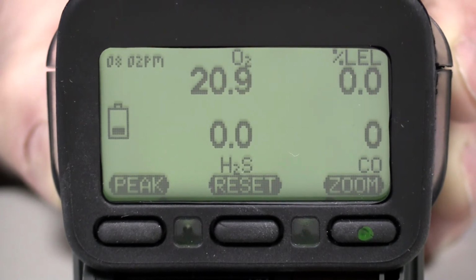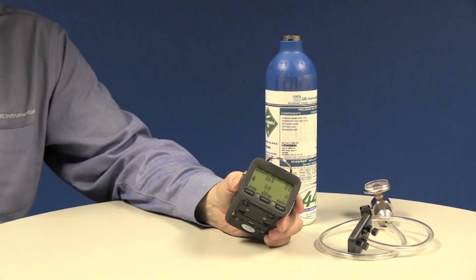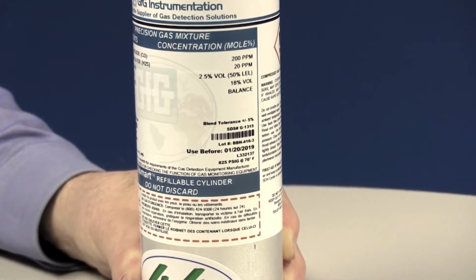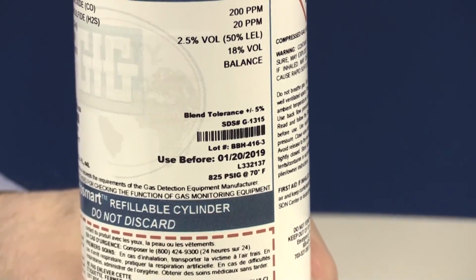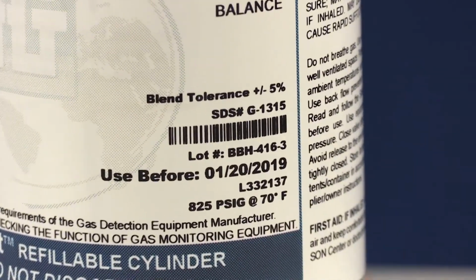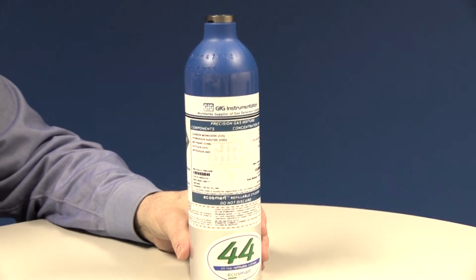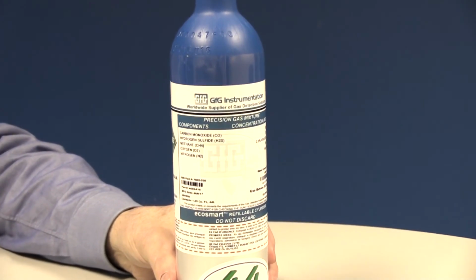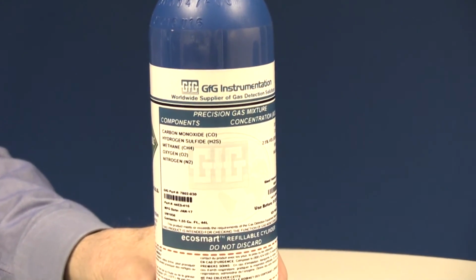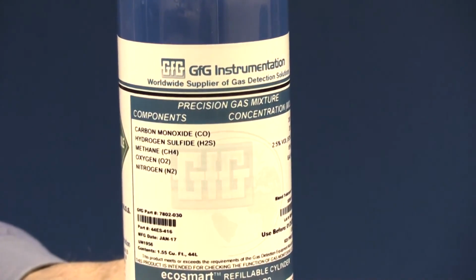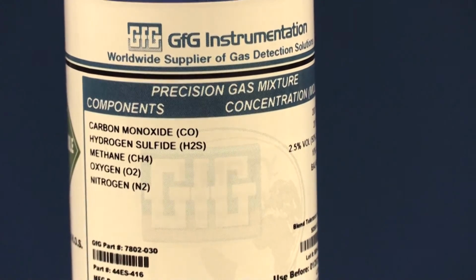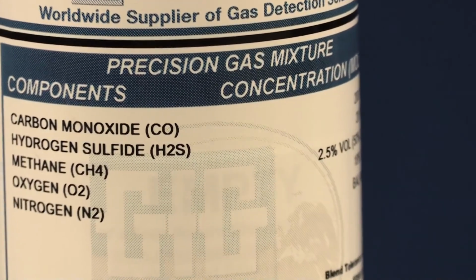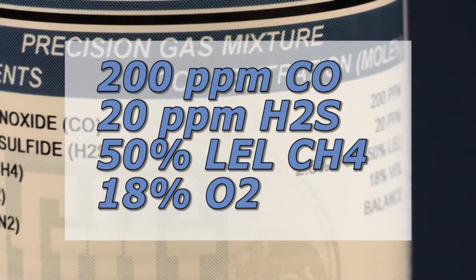During the gas autocal calibration, the accuracy of the sensors is adjusted to exactly match the concentration in a cylinder of known concentration calibration gas. Make sure you are using a cylinder of gas with the correct concentrations and that the cylinder is within dating. Calibration gas with expired dating should not be used. The gas used to calibrate the G450 should contain 50% LEL methane, or CH4, which is the chemical formula for methane, 18% oxygen, 20 parts per million H2S, and 200 parts per million CO. Do not use the gas if the label shows a different concentration for any of the gases in the mixture.